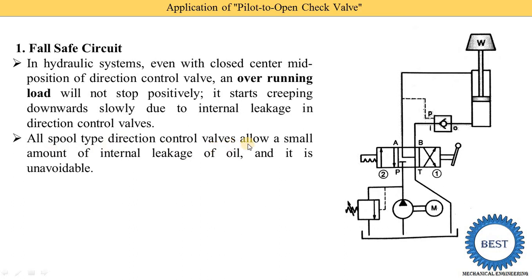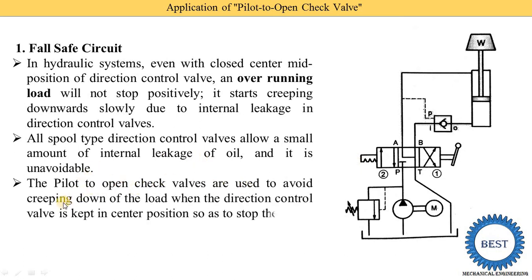All spool-type directional control valves allow a small amount of internal leakage of oil, and it is unavoidable. The pilot-to-open check valves are used to avoid creeping down of the load when the directional valve is kept in the center position so as to stop the load — meaning we need to sustain the load at a certain desired position. Now we move towards the detailed working.